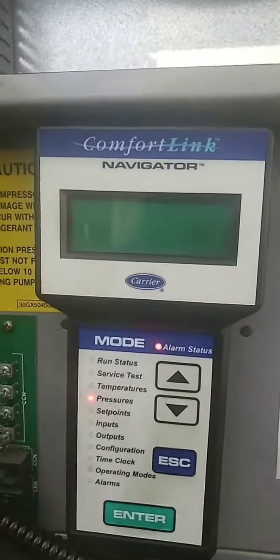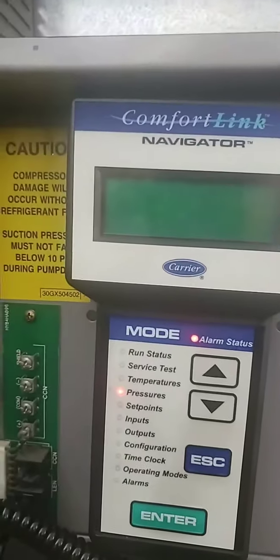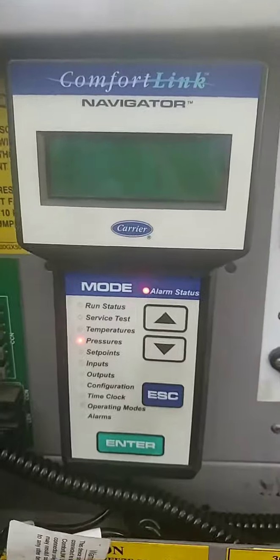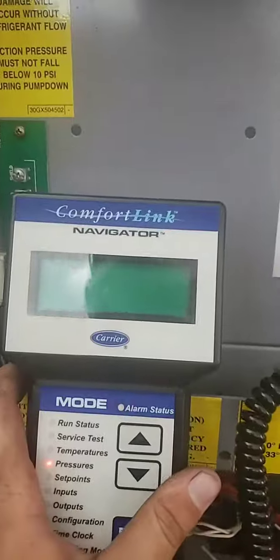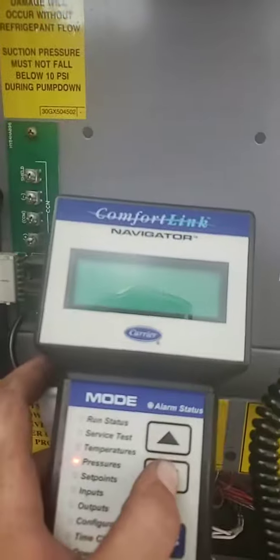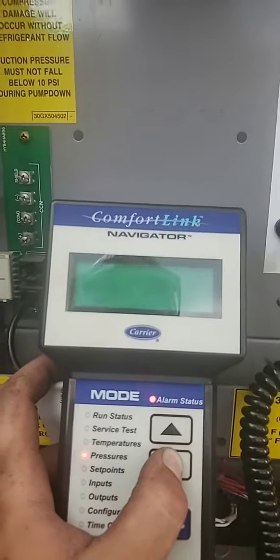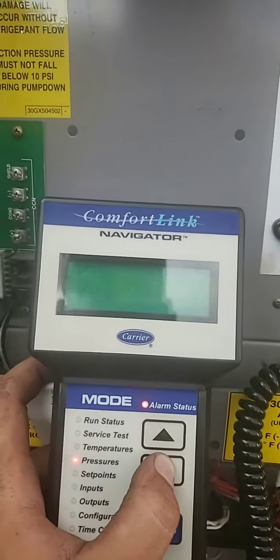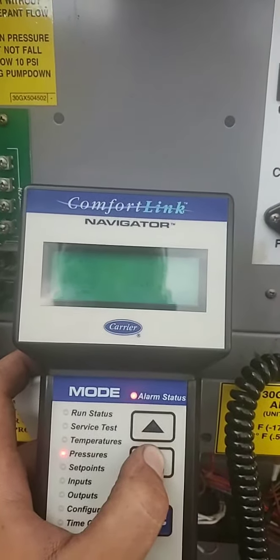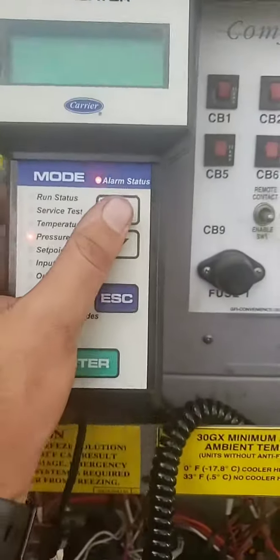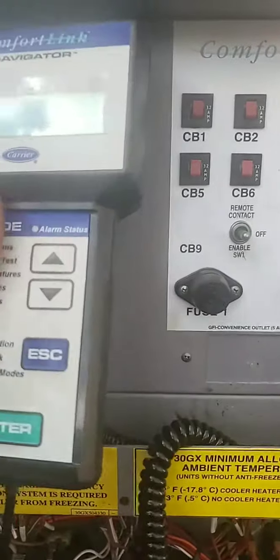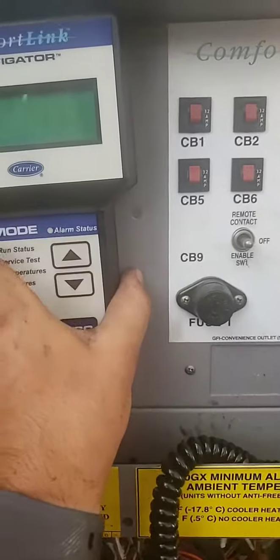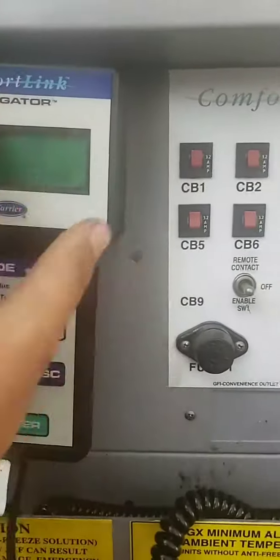Let's see if I can get refocused here. So the difference between those two, sorry guys, I'm trying to get where y'all can see it, is your DO, your oil differential. If we scroll down even more, you'll see the A1. That is the oil filter differential pressure. So that's the actual pressure drop across your oil filter. That's the one that you'll have to monitor on a routine basis. Make sure it stays between the 15 and 20.